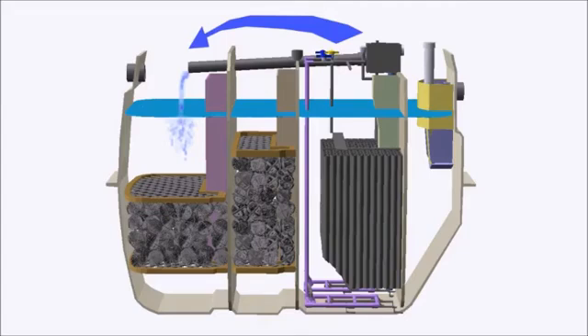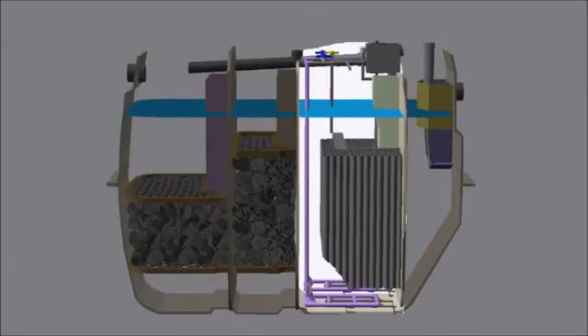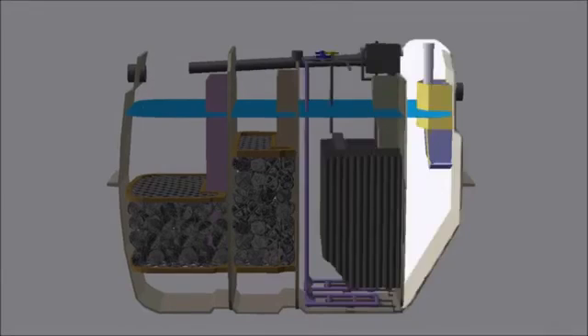This is the denitrification filter aeration process. The solids in the water are removed in the denitrification filter tank, and the organic pollutants and nitrogen compounds are decomposed by microorganisms in the contact aeration tank. Then the water is agitated by a pump to promote the denitrification reaction by microorganisms while solids in the treated wastewater are separated in the sedimentation tank.